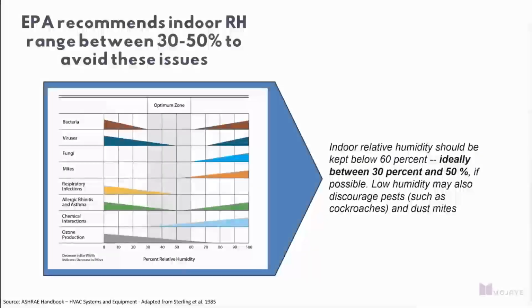And then finally, the EPA does recommend, this was beat to death during COVID, but I think it's actually a very valid message here for decoupled latent designs. The EPA does recommend that the indoor relative humidity range, the best range for humans in buildings, is between 30 and 50% relative humidity. Designing at 75/50% RH for your terminal units is fine, but there is the opportunity to decouple your latent, provide a drier space inside, and still be well within and frankly in a more comfortable zone from an IAQ standpoint and a health standpoint within buildings.